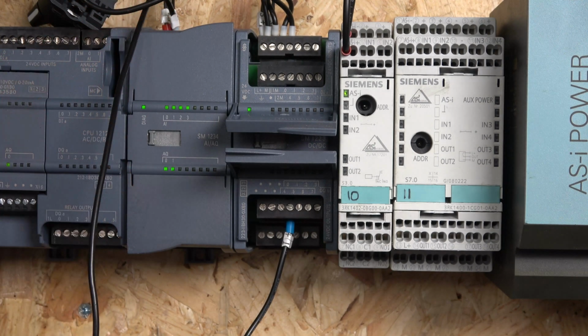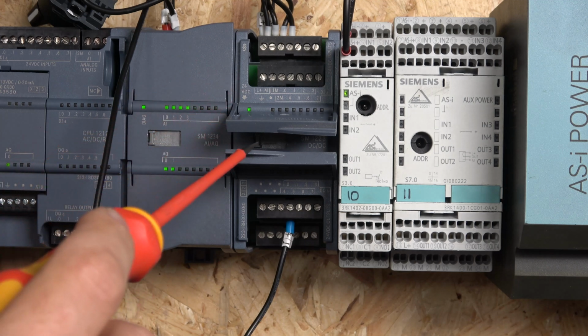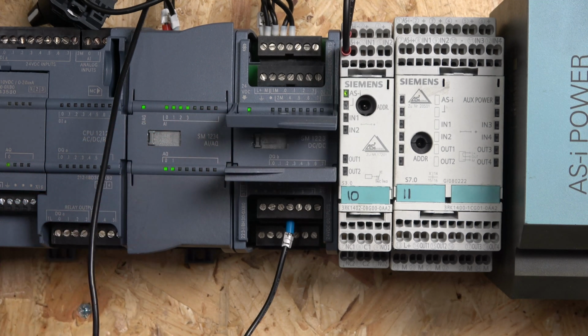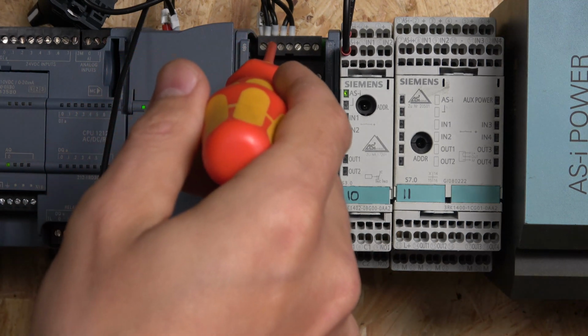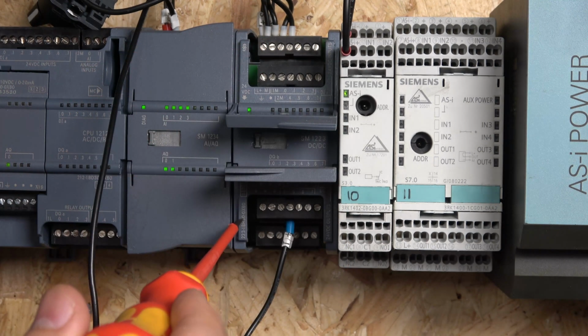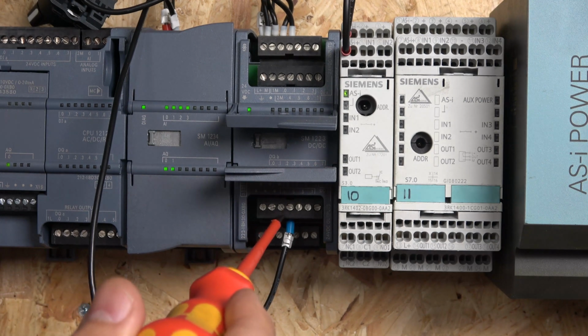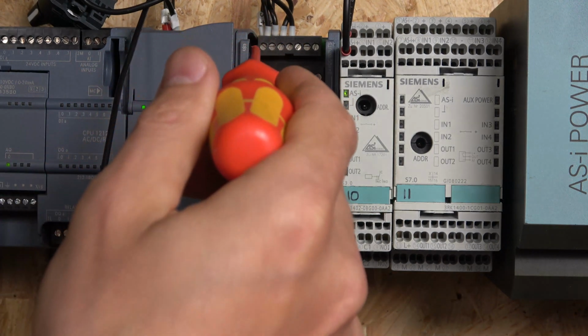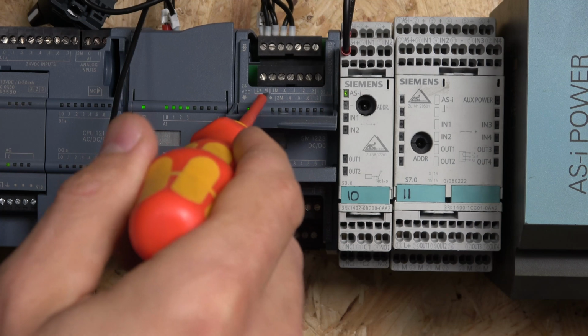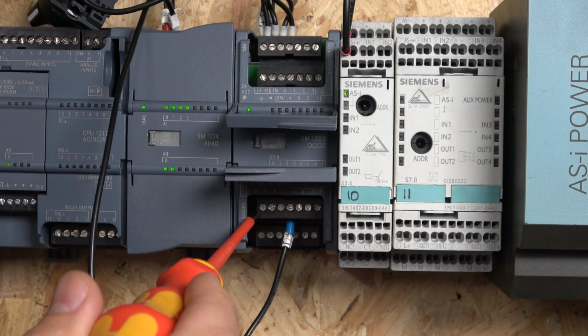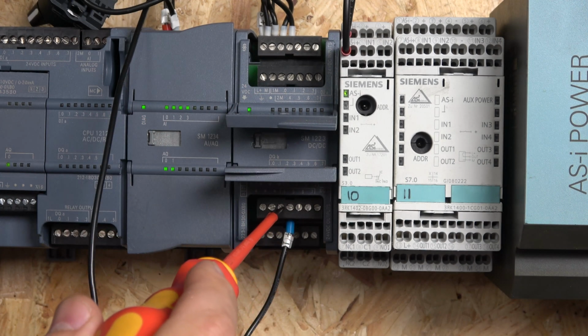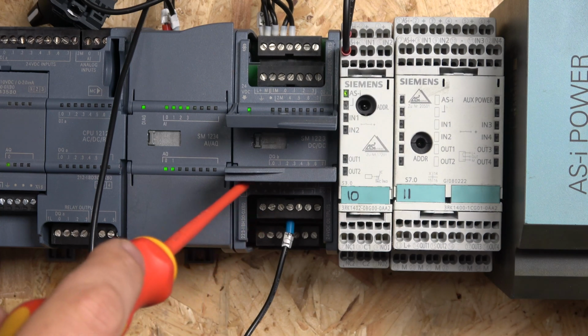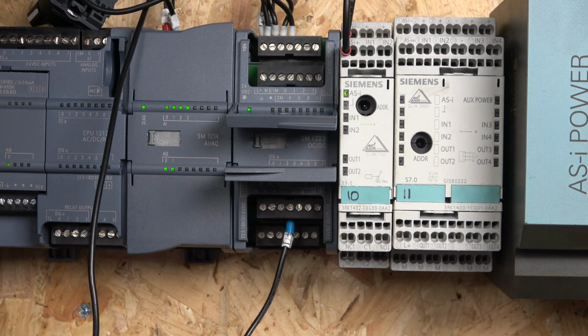Another thing is that this card is fairly unique in how you would usually wire on other PLCs. This power supply in here already powers your terminals right here on the bottom. We're going to get to that in a minute. Try to remember, these two, L plus and M, are already powering your terminals down here. All you need to do is run the cable out, and as soon as it comes on, it outputs 24 volt DC.